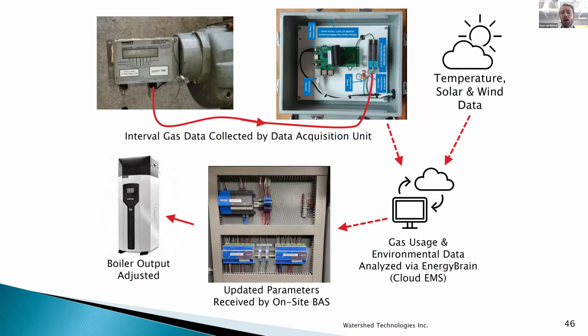And that feeds into our server, our central database called Energy Brain, which also pulls in environmental data about the temperature in the area, the sun conditions, and wind data. So if you have, for example, a south zone, we can reduce the temperatures a little bit when it's sunny. And then our server processes that data, optimizes the set point, and sends it to the on-site building automation system, which then adjusts the boiler output accordingly.